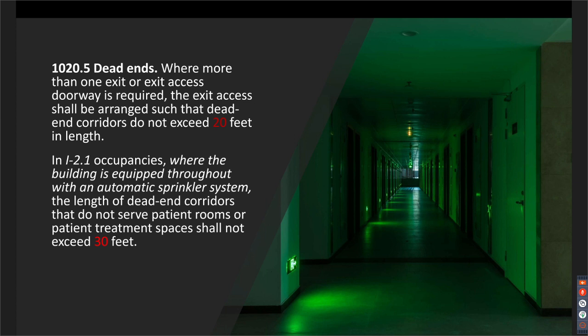So dead end requirements. The beginning portion of this hasn't changed with the code. Where more than one exit or exit access doorway is required, the exit access shall be arranged such that the dead end corridors do not exceed 20 feet in length. And then a new part of the code: in I-2.1 occupancies where the building is equipped throughout with an automatic sprinkler system, the length of dead end corridors that do not serve patient rooms or patient treatment spaces shall not exceed 30 feet. So the general requirement is you cannot have dead ends that exceed 20 feet. If you have areas that patients are not in, then you could have a dead end that goes to 30 feet. But please remember, that's only for areas where the patients are not.